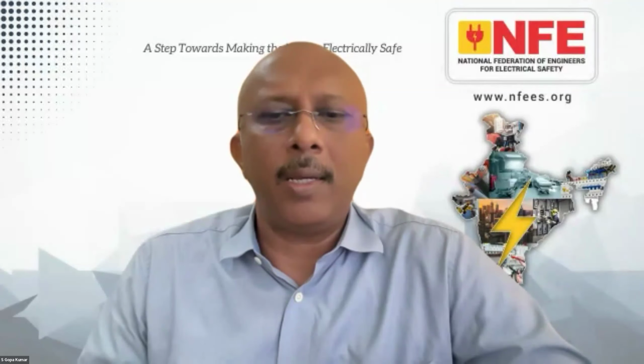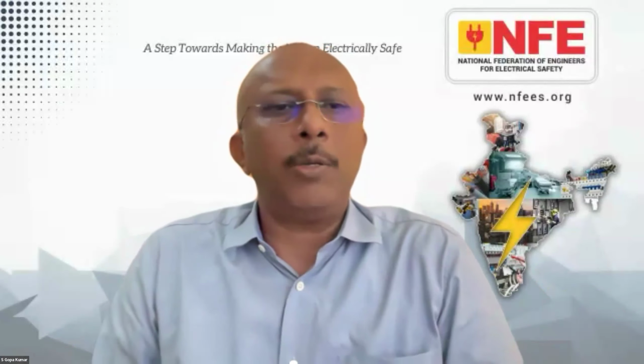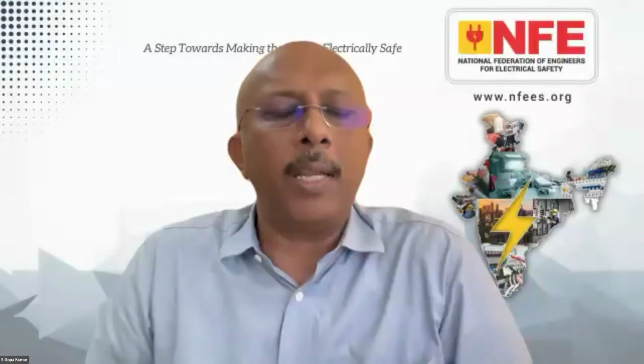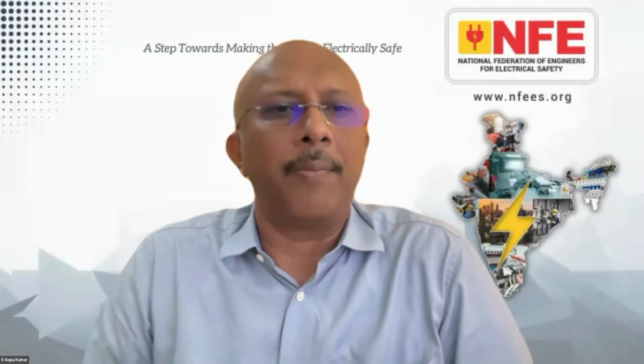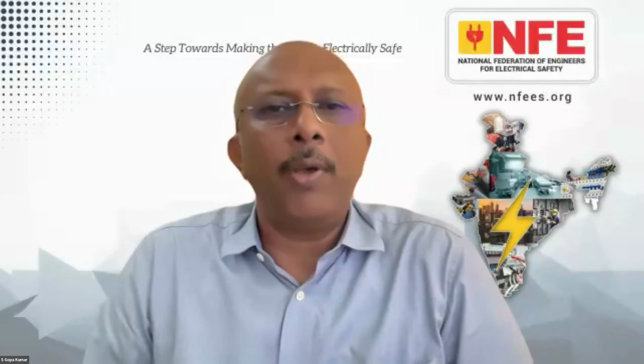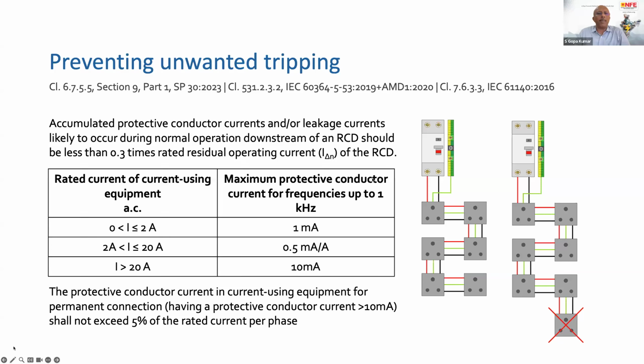Krish, you have that table probably, if you can. It was there in the slides itself. I will just share it. Yeah. So the maximum allowed leakage current from any equipment, irrespective of its current, is 10 milliampere. The requirement depends on the nominal current of the device: 0 to 2 amperes, 1 milliamp of leakage current; 2 amperes to 20 amperes, 0.5 milliampere per ampere; anything in excess of 20 amperes, 10 milliampere.